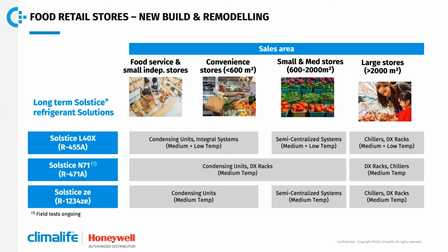For example, R455A can be used in MT, medium temperature, but also in low temperature, regardless of the store size. R471A and 1234ZE both can be used for medium temperature, in condensing units, in centralized or semi-centralized systems, but also in direct expansion and in chiller systems with a water loop, for example.